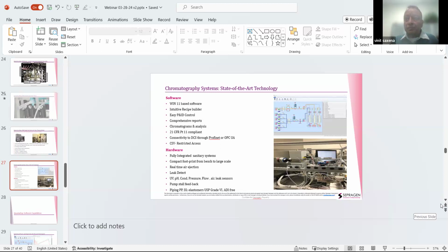And many alarm settings, customized settings that we can have for not only pressure and air leaks, things like that, but for process values. So you want conductivity within a certain range or pH within a certain range. Outside of those ranges, the buffer can be ejected, or you can get a process tolerance alarm.